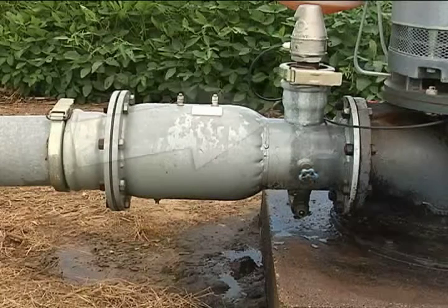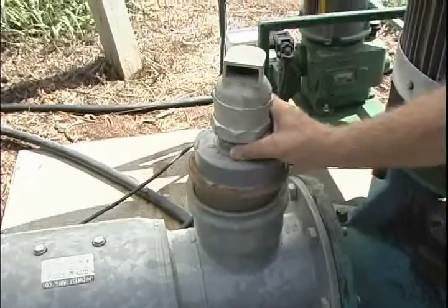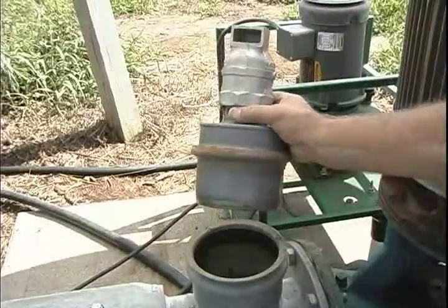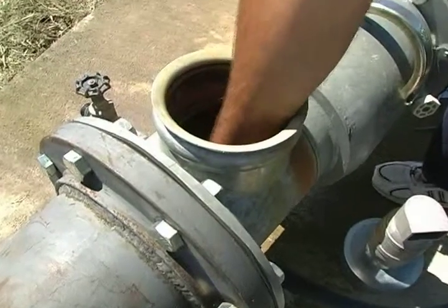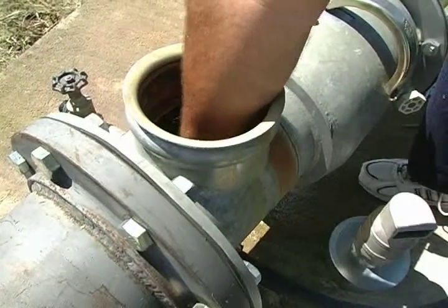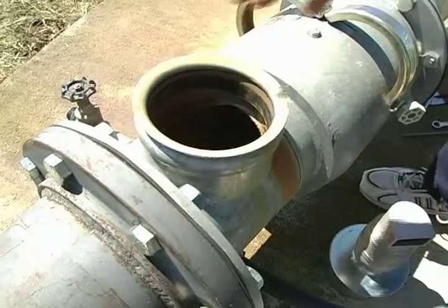Nebraska regulations also call for an inspection port or other viewing device. Ordinarily, the vacuum relief valve connection serves as the inspection port. Its purpose is to allow inspection of the irrigation pipeline check valve to ensure that it seats properly and there is no leakage past it.